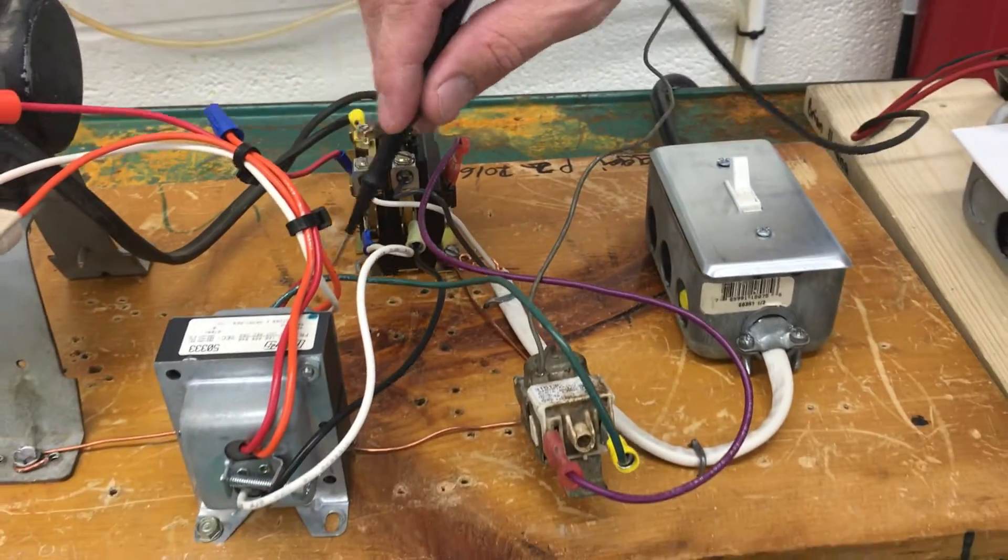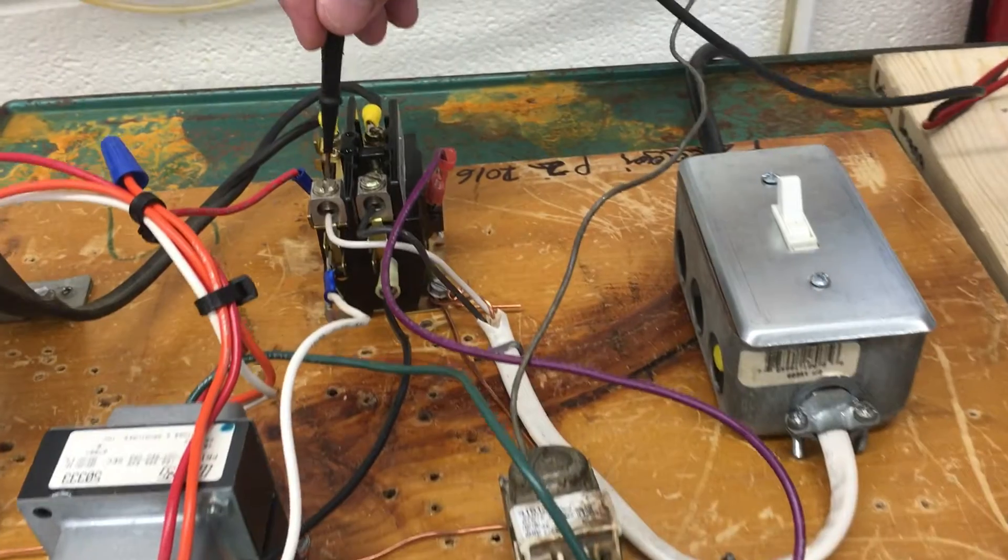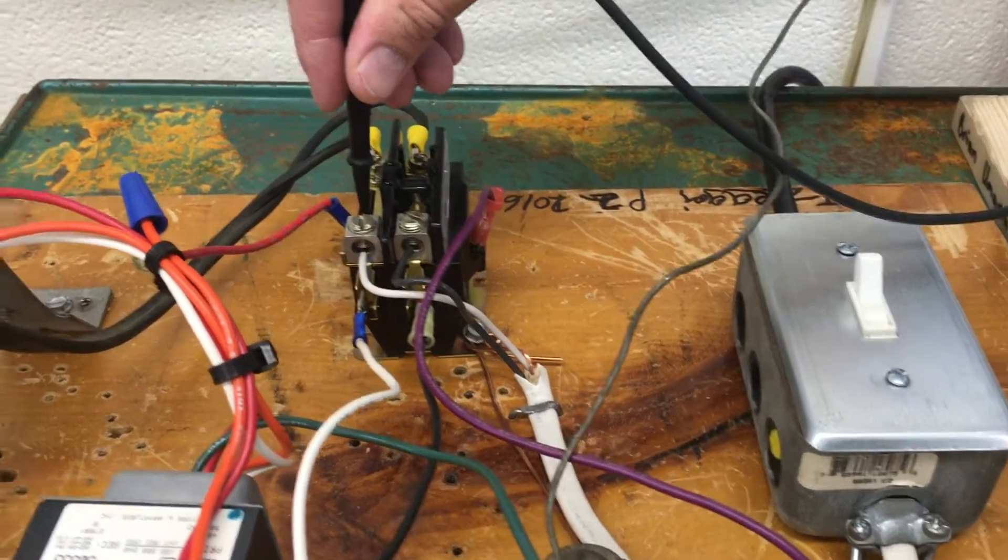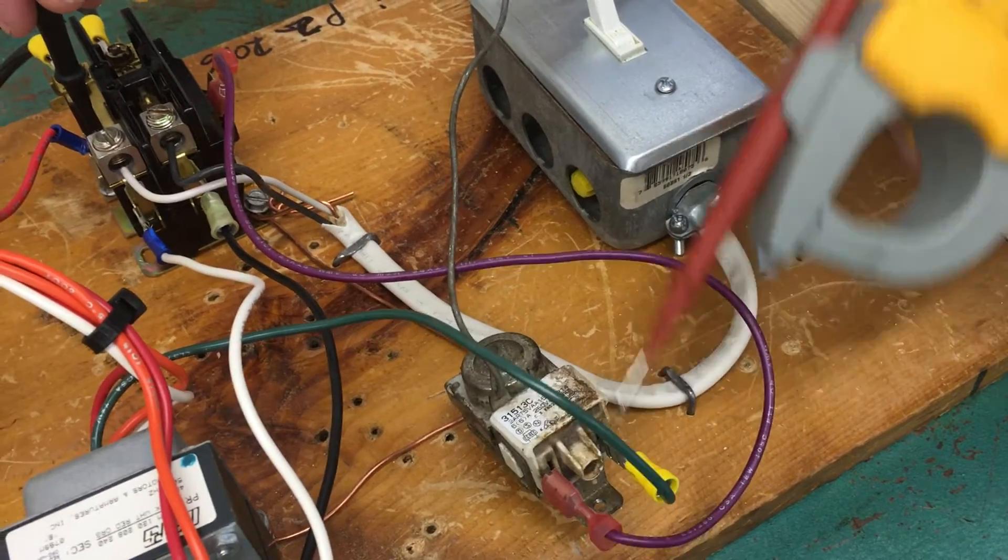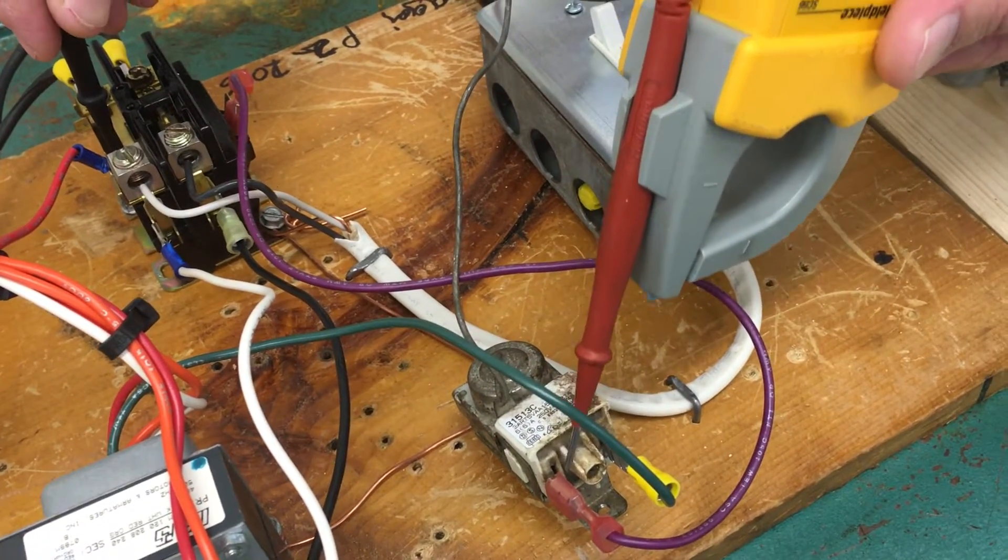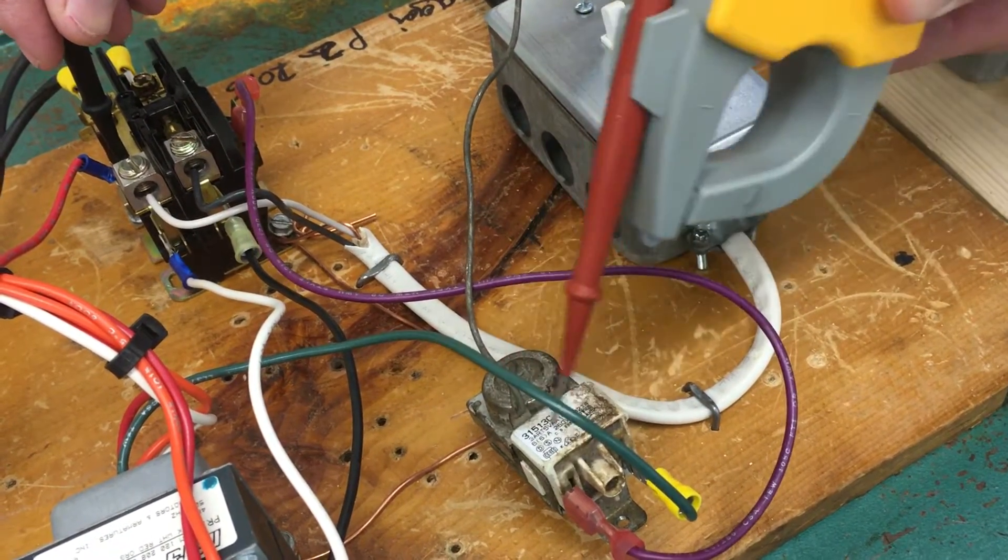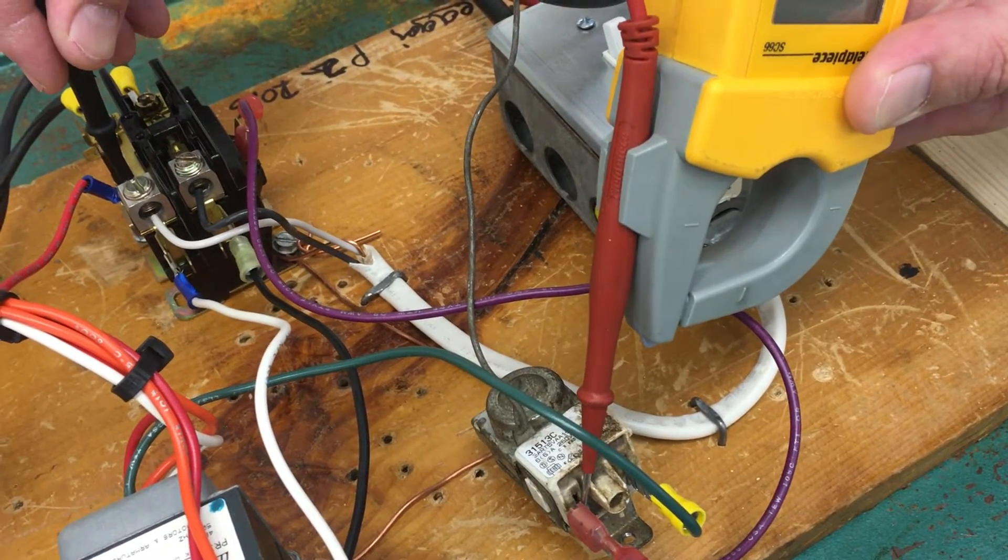I also want you to measure, so we have a common terminal coming back from the transformer over here on this side of the coil, and I want you to measure across the thermostat. Be careful right here that it doesn't touch any other metal or ground, and you're going to measure both sides across the thermostat.